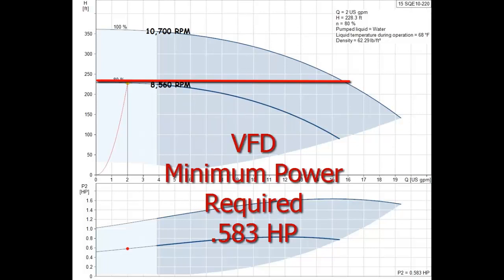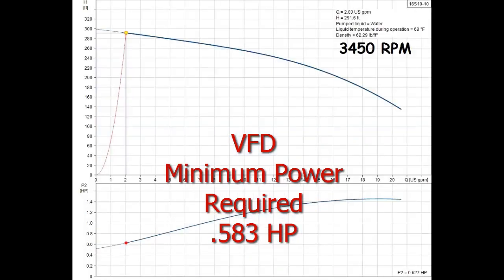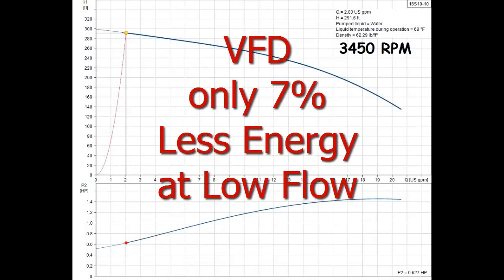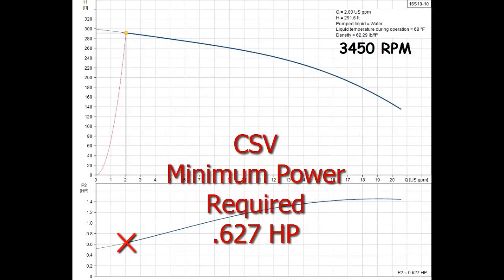Since 0.583 horsepower is the least energy use possible with a variable speed pump, there is only a 7% difference in the 0.627 horsepower needed by simply restricting a normal full speed pump with a cycle stop valve or CSV.